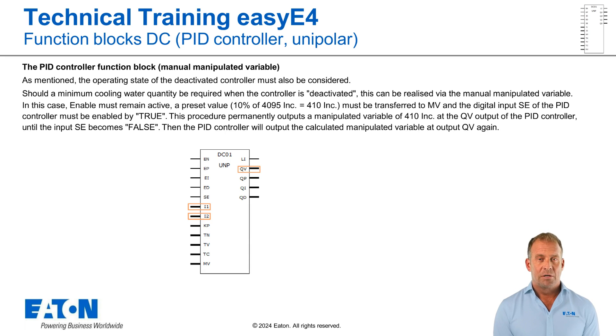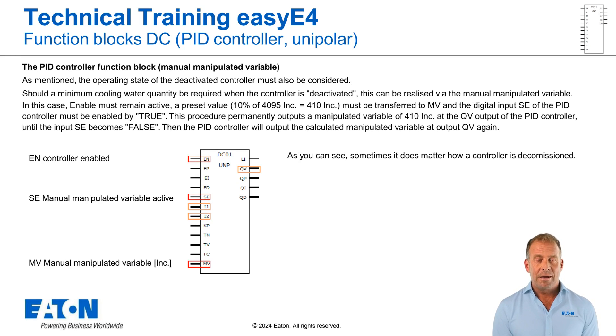For this task there is a solution: the manual manipulated variable of the PID controller. Should a minimum cooling water quantity be required when the controller is deactivated, this can be realized via the manual manipulated variable. In this case, the input enable must remain enabled. A value specification in increments must be transferred to the input MV, and the digital input SE of the PID controller must be enabled. The 10% target is calculated as follows: 4,095 maximum increments times factor 0.1 for 10% equals 410 increments. This procedure permanently outputs a manipulated variable of 410 increments at the QV output until the input SE becomes false.